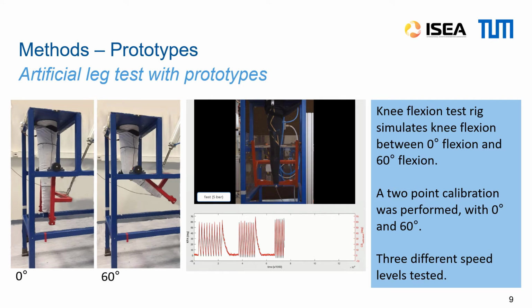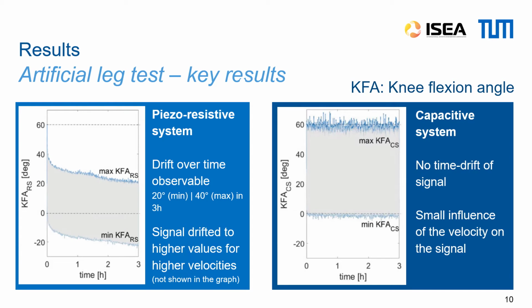A rotary sensor with an accuracy of 0.1 degree was used to record the amplitude and velocity of the movements of the test rig. The behavior of maximum and minimum flexion values of the long-term tests are shown in these figures. A relaxation of the resistive sensor signal over 3 hours of 40 degrees for the maximum values and 20 degrees for the minimum values was observed.